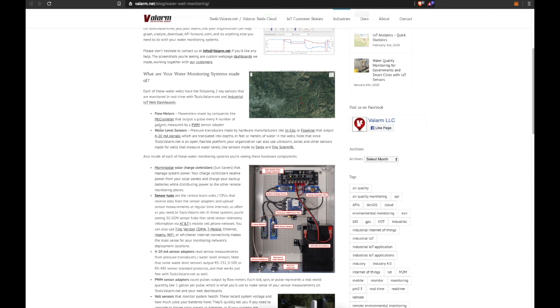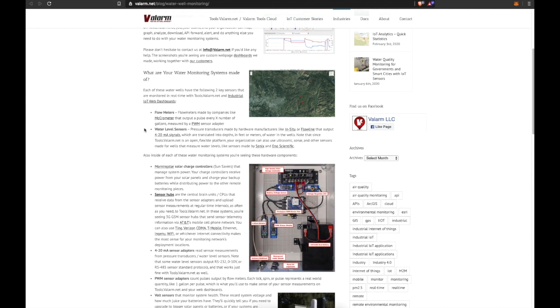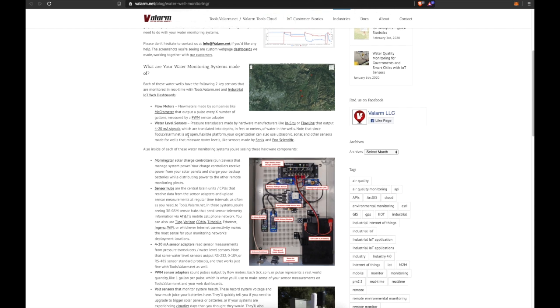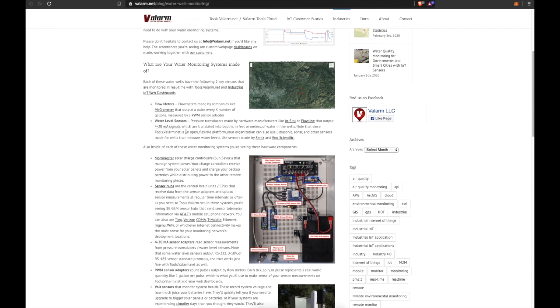Second up, the other key sensor that you see in all these water wells are water level sensors. Gotta know how much water is in your well. Pressure transducers made by hardware manufacturers like In-Situ or Flowline output 4 to 20 milliamp signals, which are then translated into depths in feet or meters of water that's in the wells.